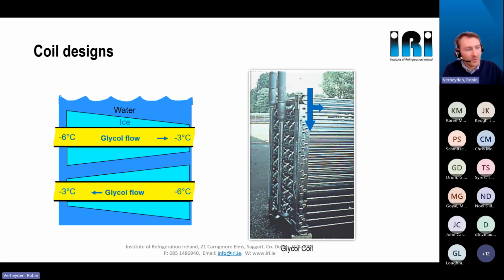Because with glycol, unlike ammonia, there is a temperature difference as the fluid passes through the coil. You'll see it here in the schematic: it enters at -6 and comes out of the coil at -3. That means the LMTD, or temperature difference, between water and coil is bigger at the beginning than at the end. This makes the ice build not uniformly, but more like a cone instead of a cylinder. It's not a big difference, but you can see it.